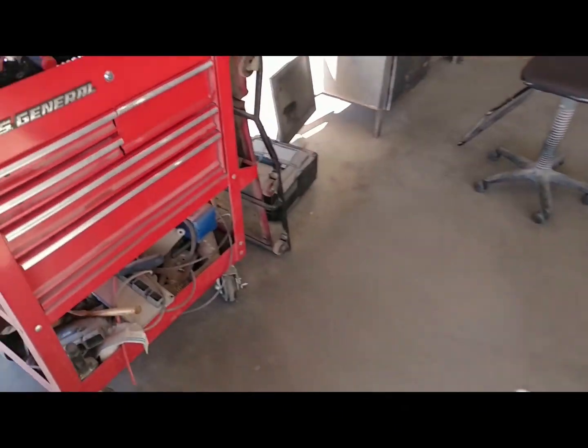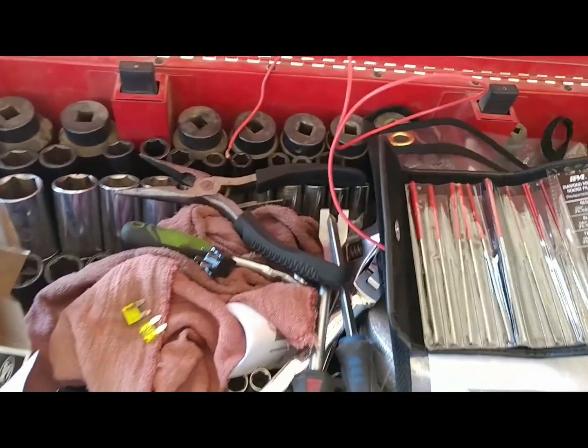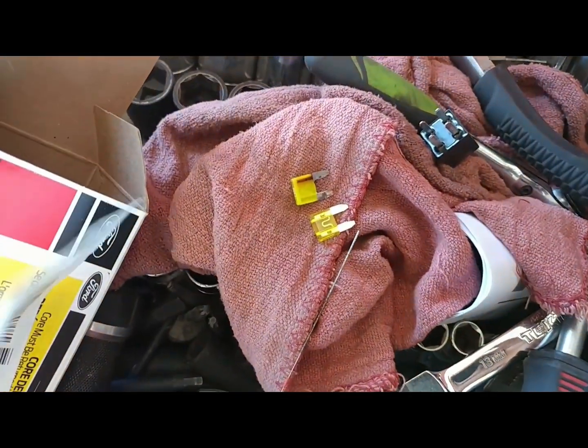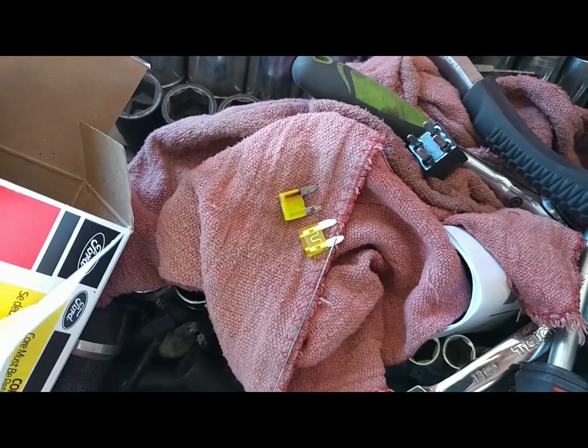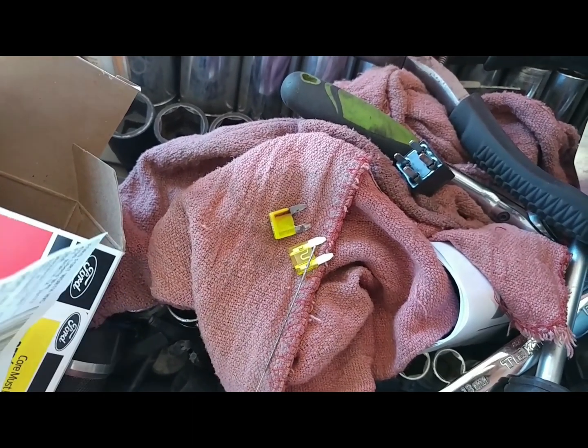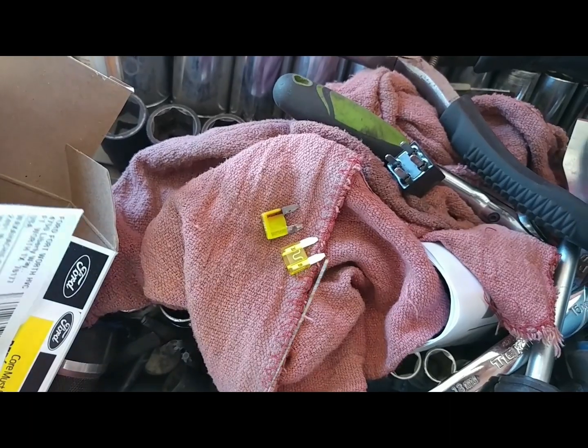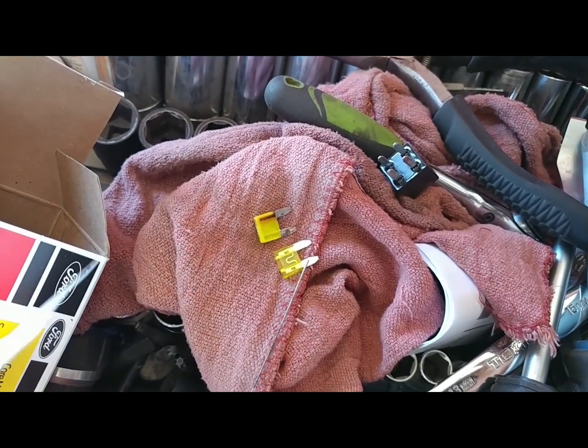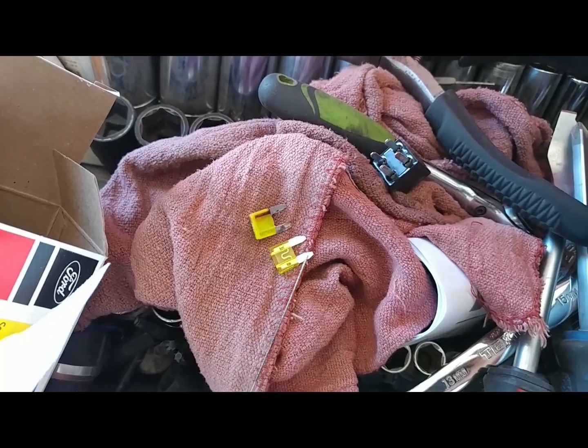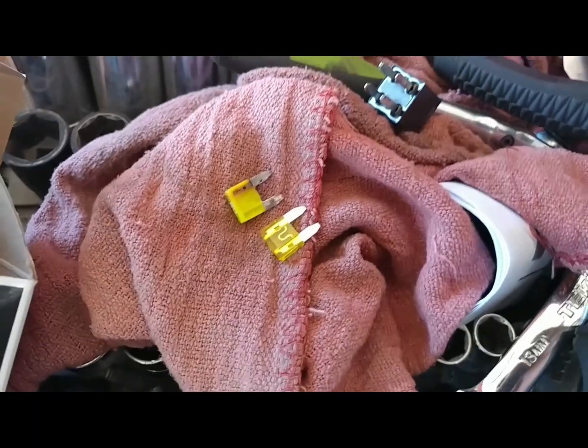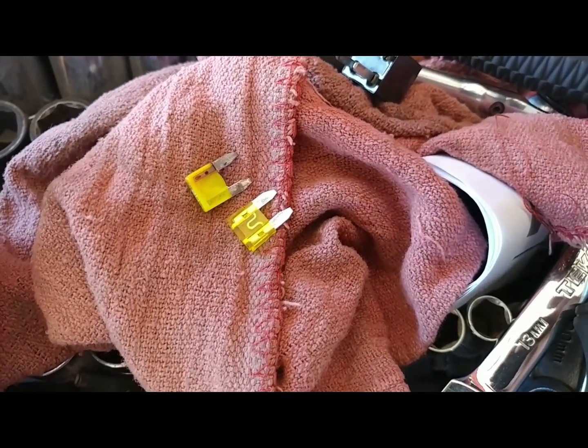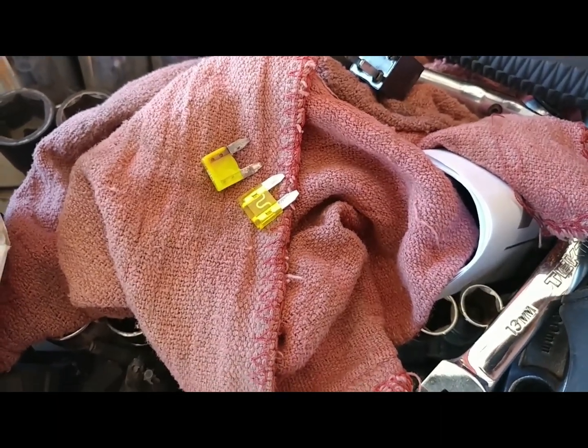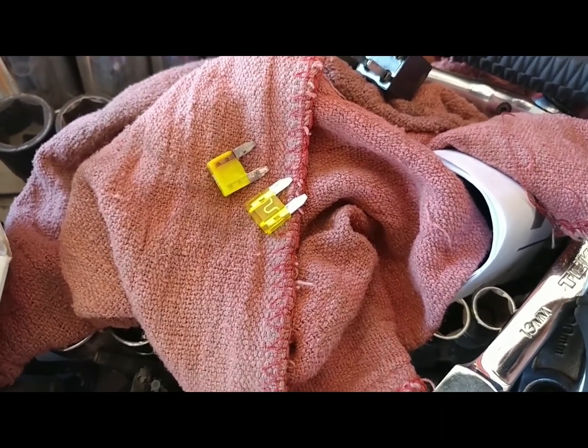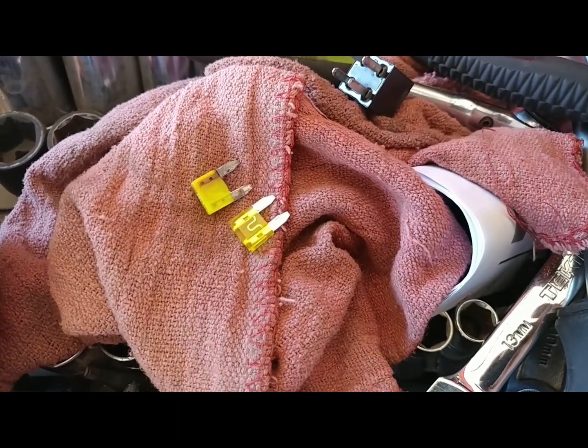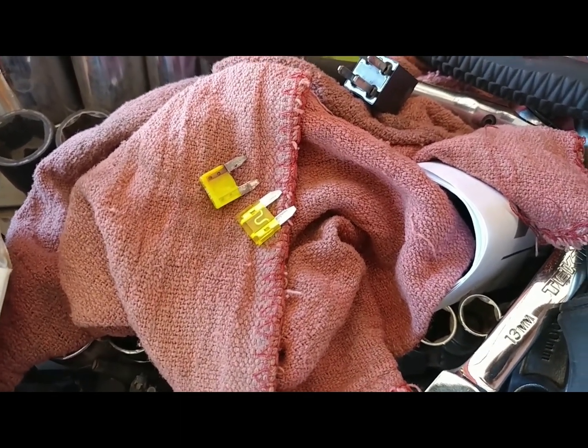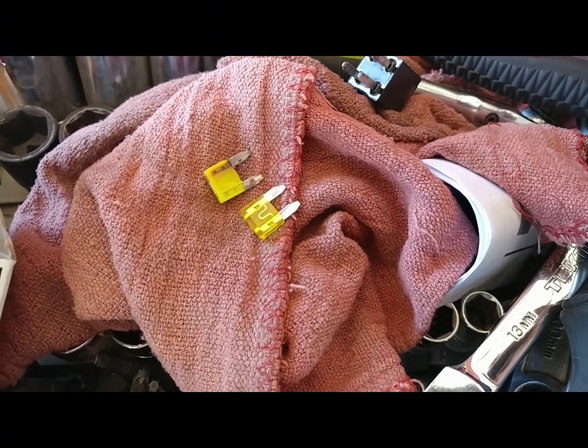So as I just mentioned, we've lost the spring that holds the fuse in place and provides positive pressure against each of these blades. There's a way to overcome that without replacing the actual fuse block itself, which would cost the customer quite a bit of money. I'm going to run it by them and see what they want to do, but I've used this method in the past. I'll prepare the fuse the way I normally have, and you'll see how I overcome that spring.